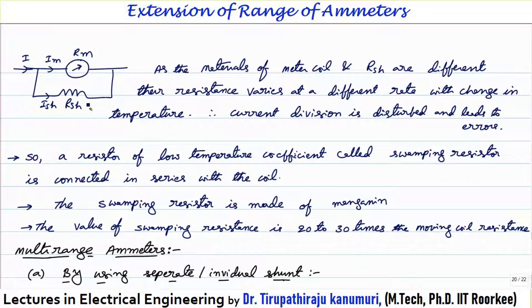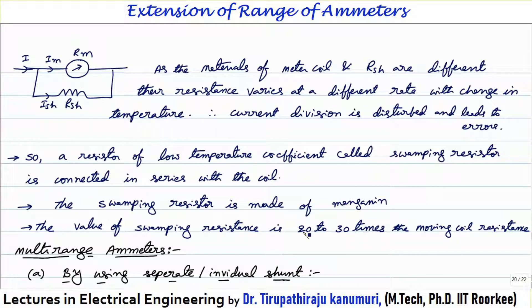To avoid the effect of temperature variations, the meter resistance should also behave like the shunt material. So a swamping resistor made of manganin is connected in series with the meter coil. The total Rm becomes the sum of the coil winding resistance plus the swamping resistor resistance. The swamping resistor is generally taken as 20 to 30 times the resistance of the coil, so that the temperature-induced change in coil resistance is negligible by comparison.